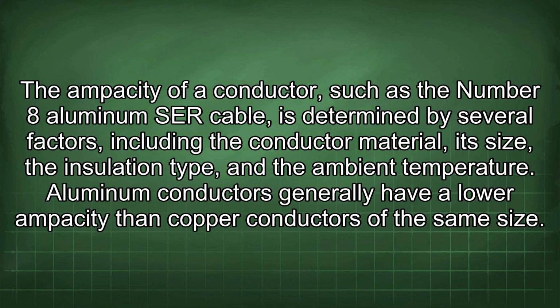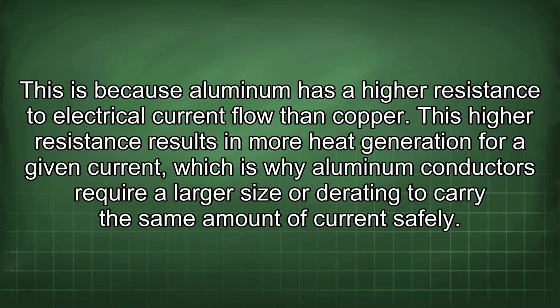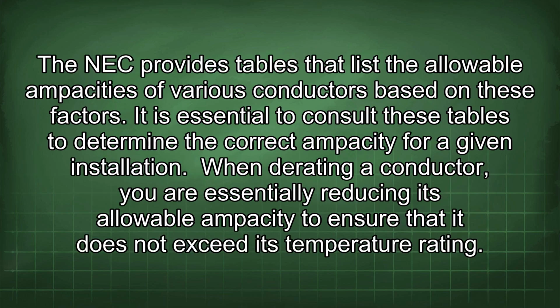Aluminum conductors generally have a lower ampacity than copper conductors of the same size. This is because aluminum has a higher resistance to electrical current flow than copper. This higher resistance results in more heat generation for a given current, which is why aluminum conductors require a larger size or derating to carry the same amount of current safely. The NEC provides tables that list allowable ampacities of various conductors based on these factors. It is essential to consult these tables to determine the correct ampacity for a given installation.